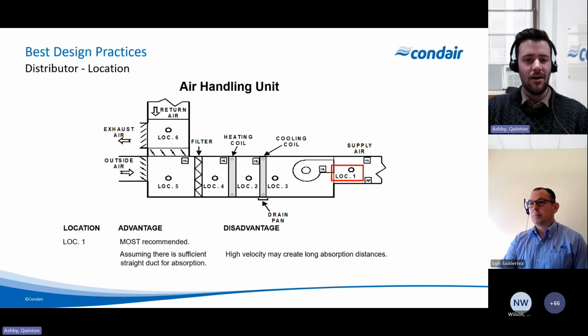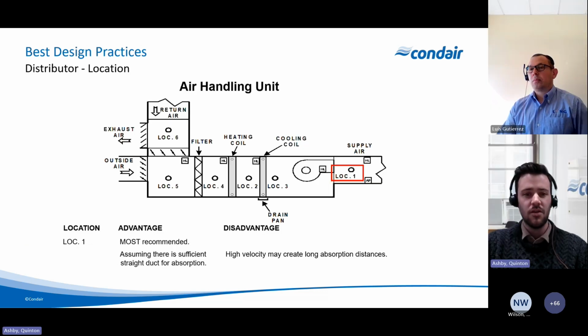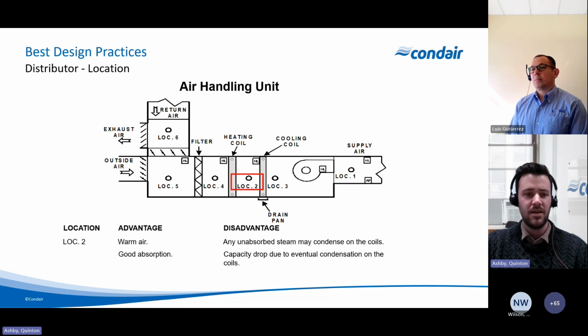Going forward, I'll touch upon this just a tiny bit. In terms of locations, supply air is a very good location. There needs to be sufficient straight duct for absorption. And we do have to be wary about velocity, which I'll touch on, but it's a good spot. The next best spot is between the heating and the cooling coil. That's a great spot for a humidifier. There's warm air, which really helps decrease the absorption distance. But yeah, we do have to make sure that there is enough distance between those two.